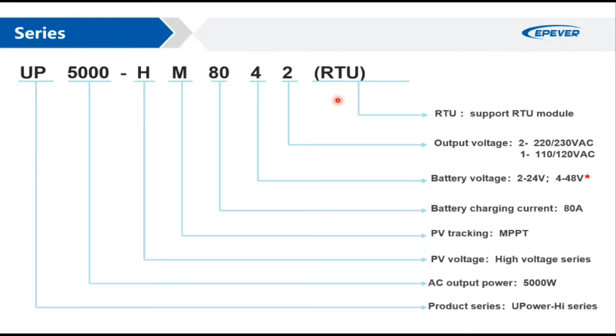So let's have a quick look at the parameters. As you can see, UPOWER HI supports both 24 and 48 volts battery systems, and the charging capacity could go up to 80 amperes in the UPHI 5000 model, and the continuous power is clear. Then we have the surge power. The surge power is normally double the capacity of continuous power. However, in some models like UPOWER 5000s, the surge power is limited to 8 kilowatts instead of 10 kilowatts, and it is a restriction derived from the power MOSFET.